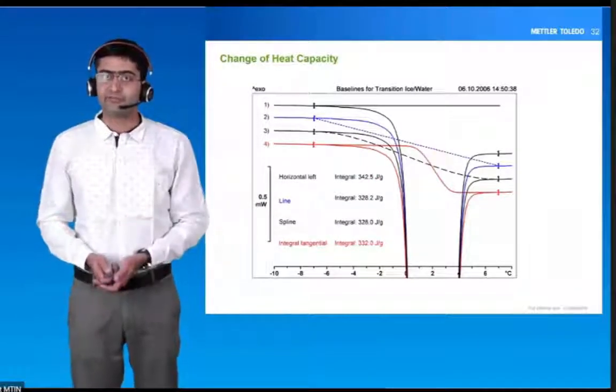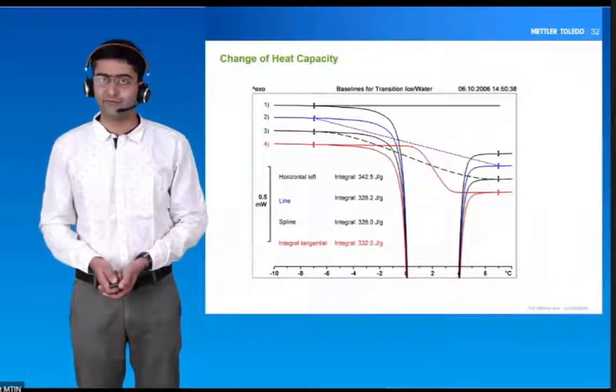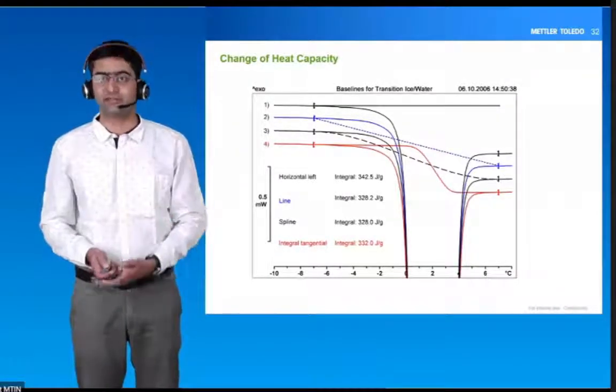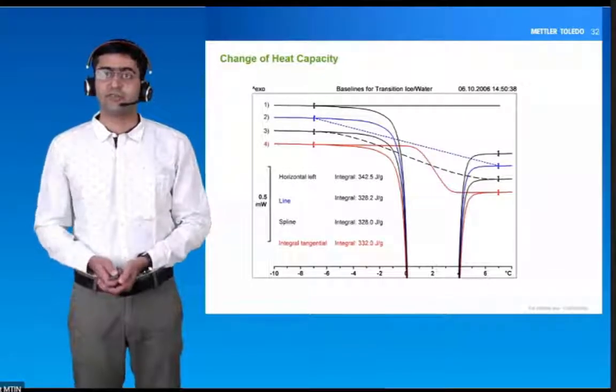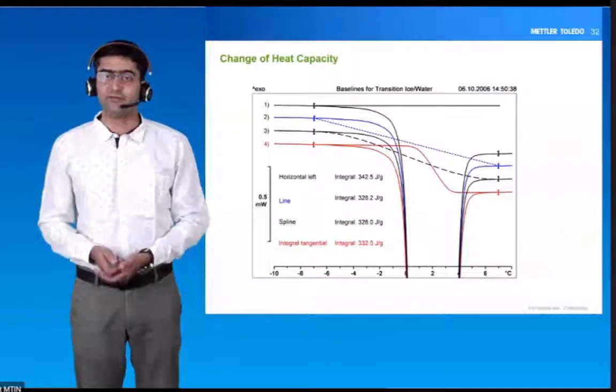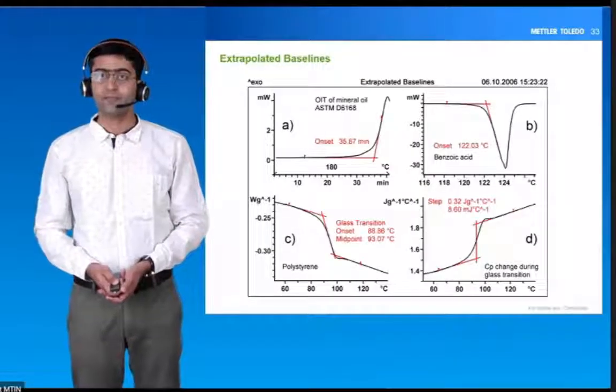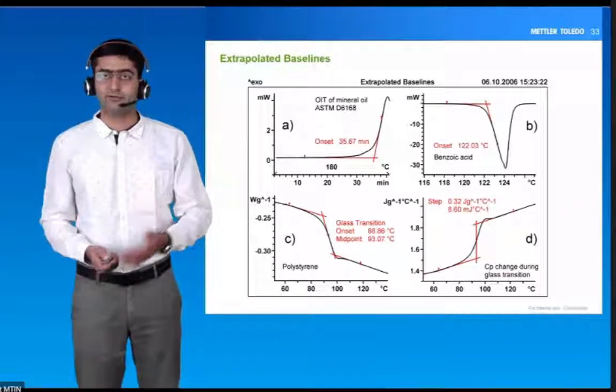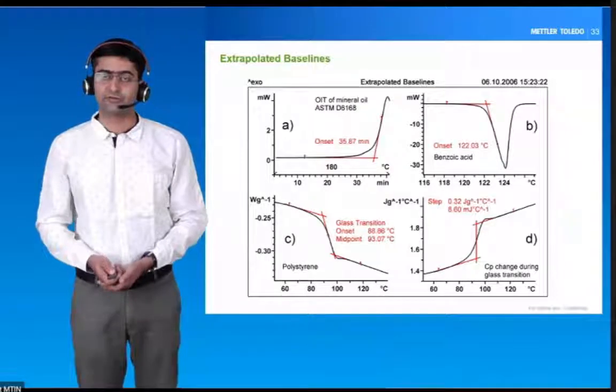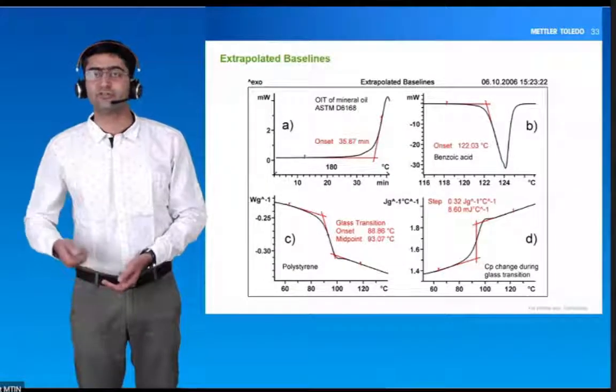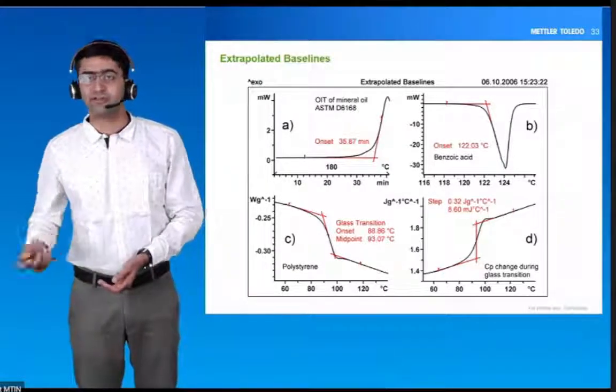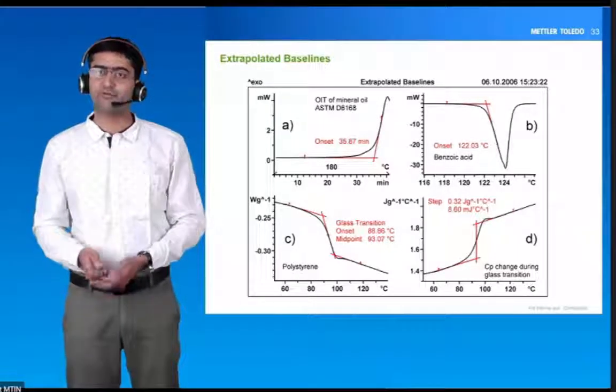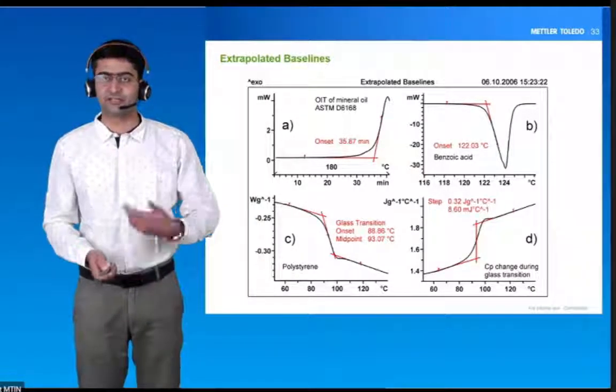What will be the effect of the baseline? For example, with the melting of water, the enthalpy value will be different if you take a different baseline — this is the effect of baseline on enthalpy value. Sometimes you also use extrapolated baselines for onset of temperature, glass transition temperature, onset of decomposition, OIT studies, or the change in CP at the glass transition event. For those kinds of analysis, we take an extrapolated baseline.